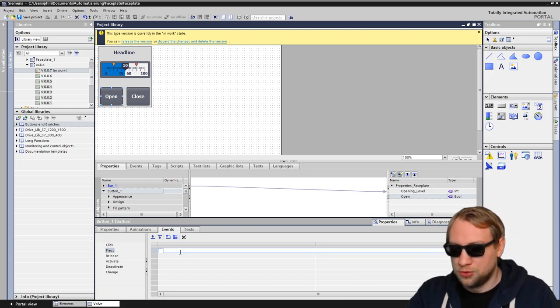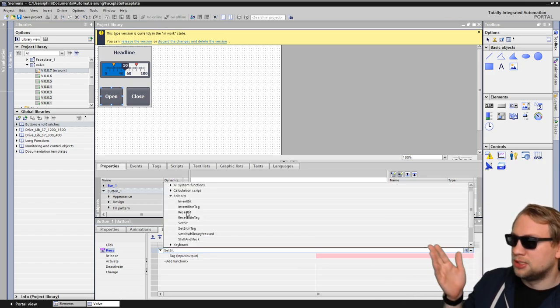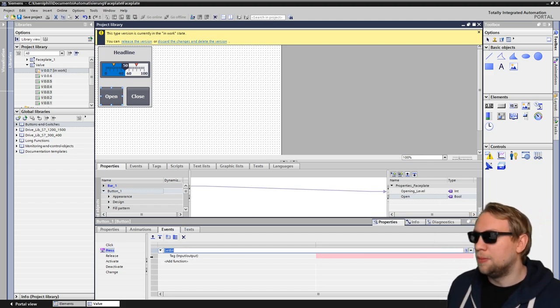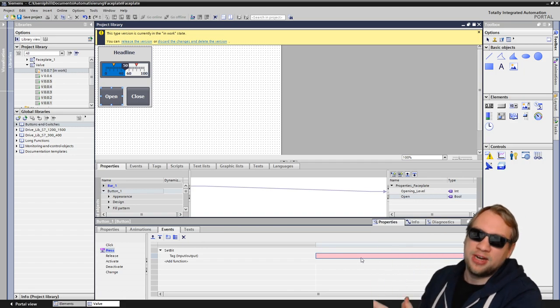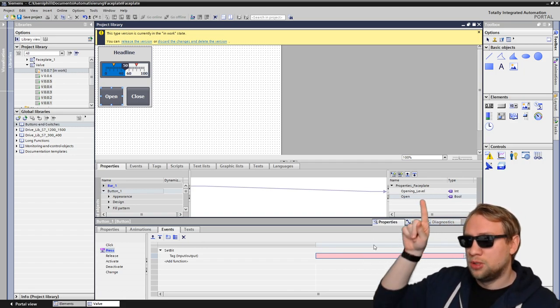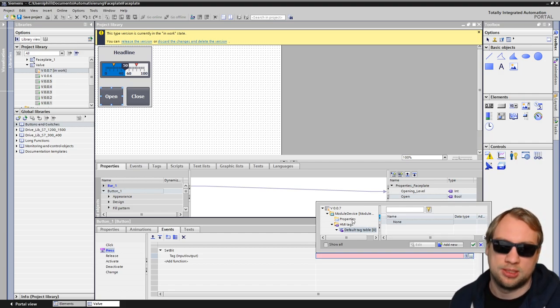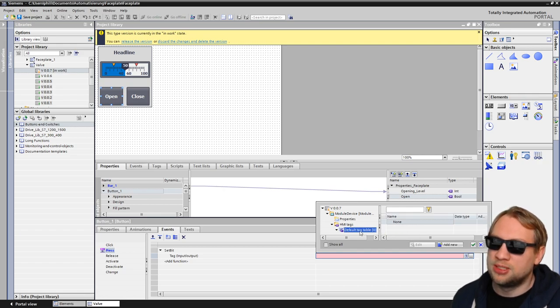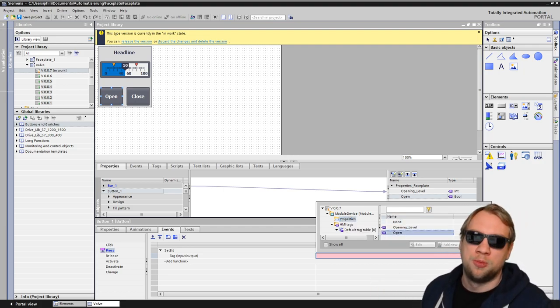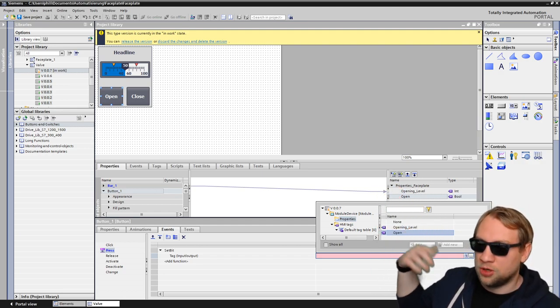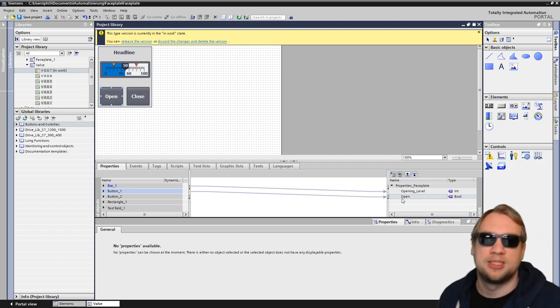On press, we want to set a bit. We can also choose that from the dropdown - there is edit bits and set bit, but that's just general HMI stuff. And there we need to now control a tag. What we want to do is not control a tag directly like valve one open or valve two open - we want to control this open variable. We can do that by pressing on the three dots here and there you see properties. I could now manually take one of those tags from my HMI or PLC, which of course would not be the right thing to do. We want to go to properties and there we have open. Look at the little arrow here - if I hit OK, you see now button one is connected to open, which makes sense.